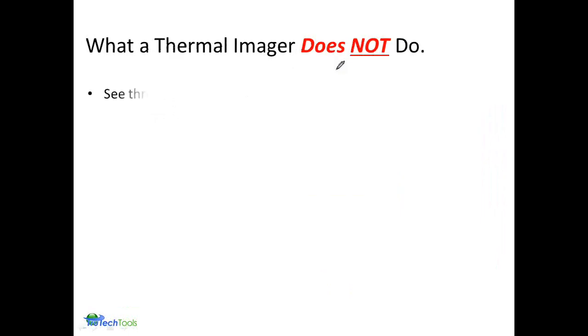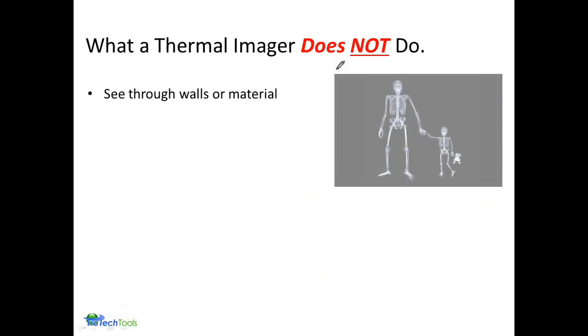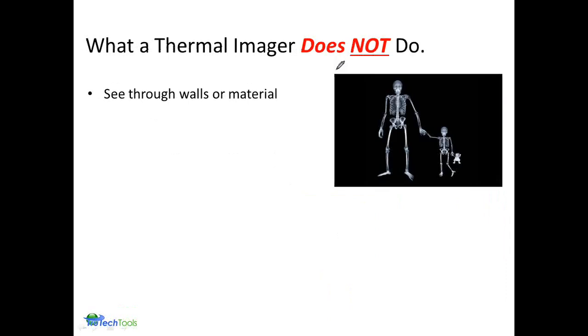Also a consideration is what a thermal imager does not do. It doesn't see through walls or materials. The only exceptions are that infrared will go through very thin plastics, it goes through the atmosphere, and it goes through the lens of your camera. Also, if you're using infrared windows, that's the same type of material the lens of your camera is made of, so it'll go through that as well. But with those few exceptions, infrared does not go through anything.